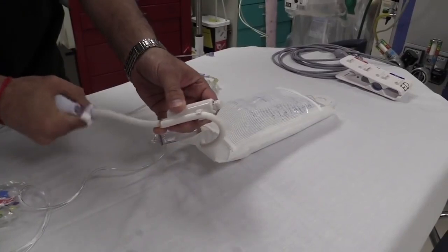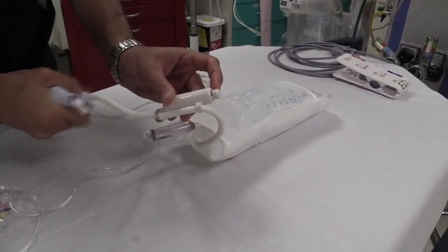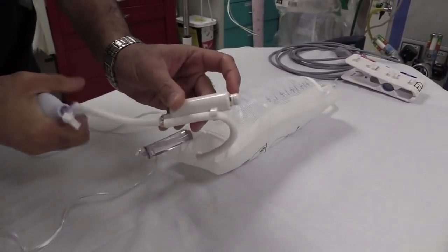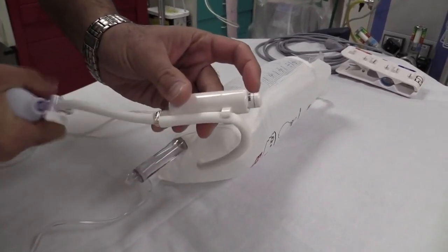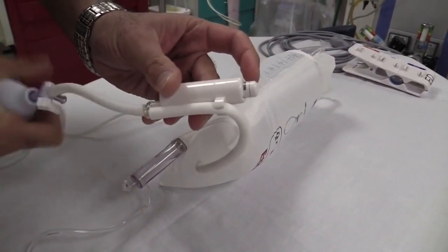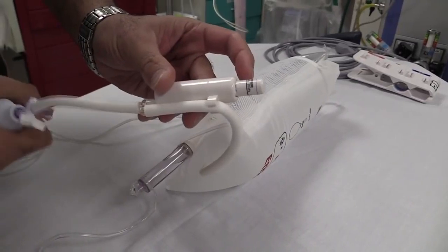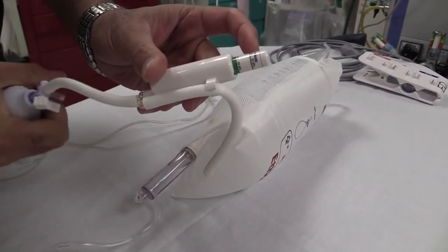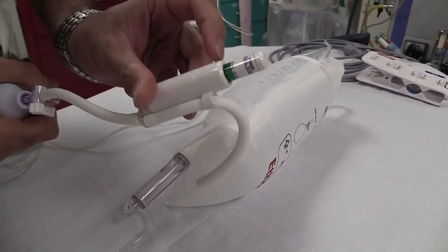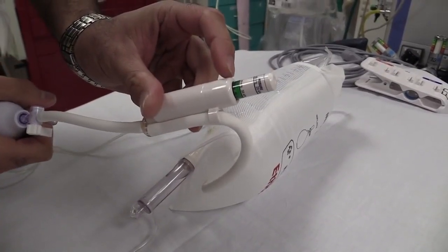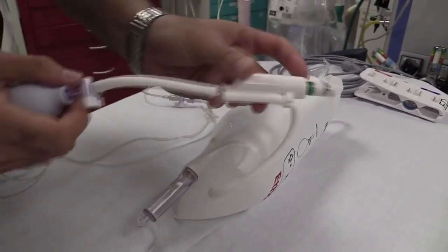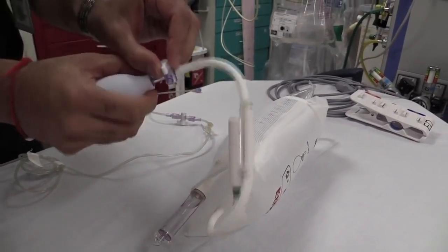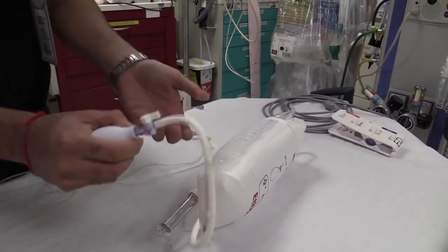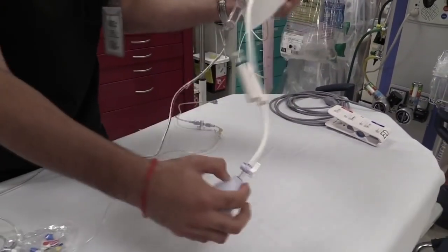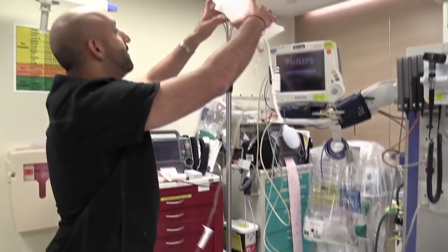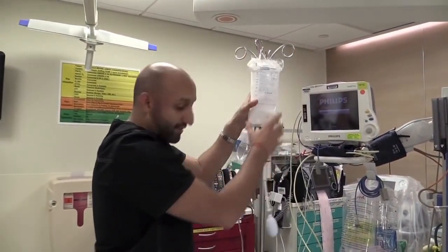Let's pump it up, and essentially here's our gauge right over here. There's a little bit of delay in this gauge, but it'll pop up in just a second. And you'll see that we're going to pump it up to a pressure. There it goes, just like that. We're going to pump up to a pressure right at 300 millimeters of mercury, and that's the ideal pressure that you want. So as soon as you're there, you're going to take the stopcock and turn it off just like this so we don't lose that pressure. And we're going to hook this up onto our IV pole. So that is step 1.